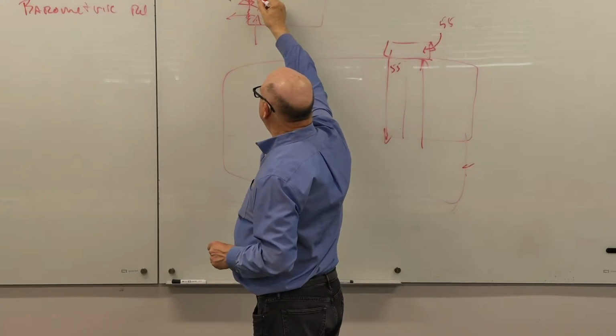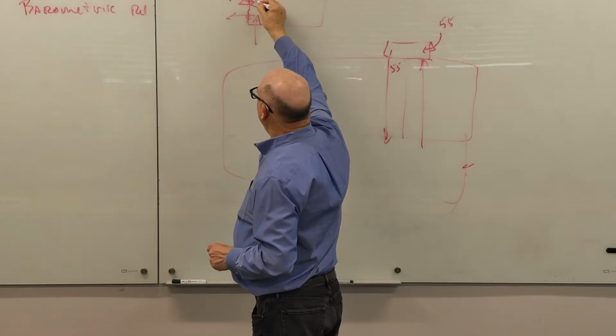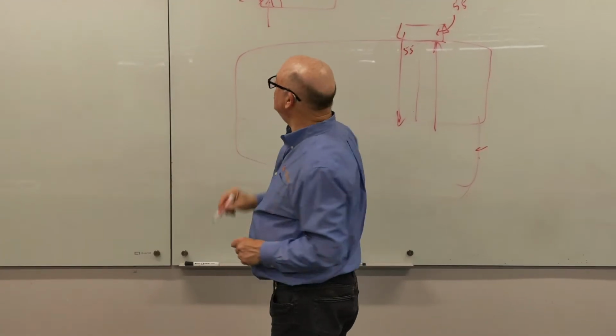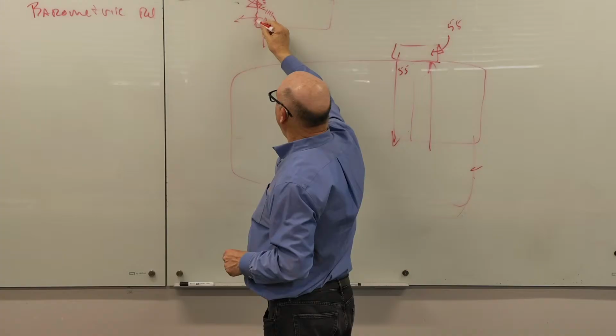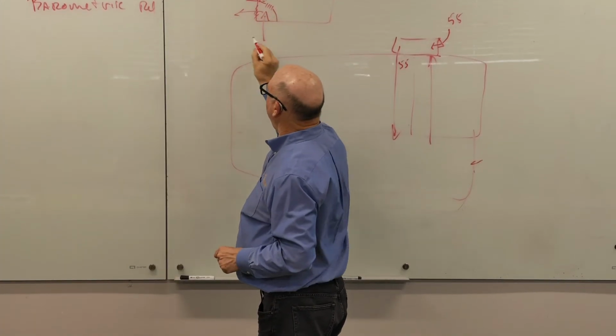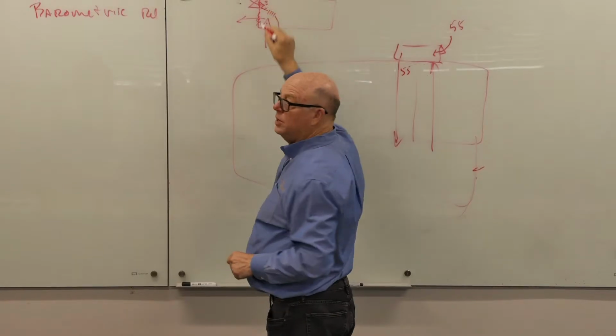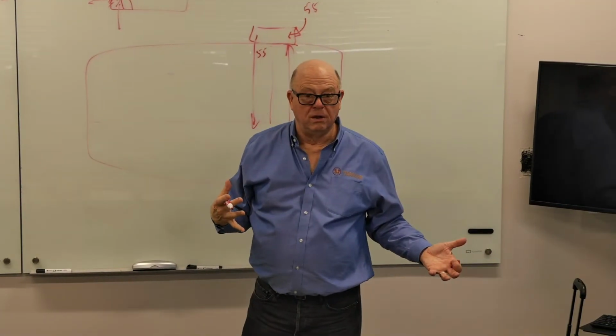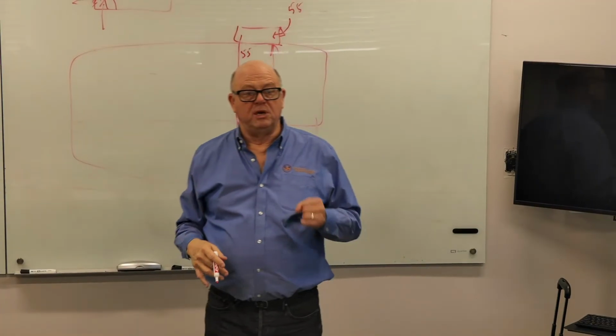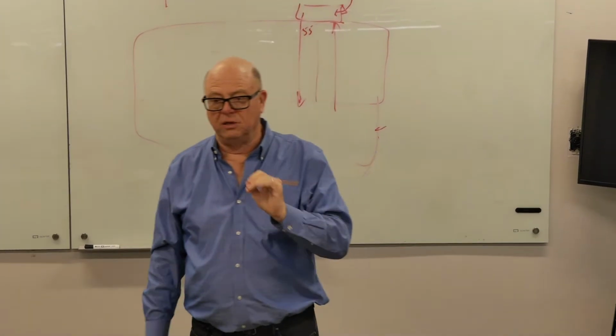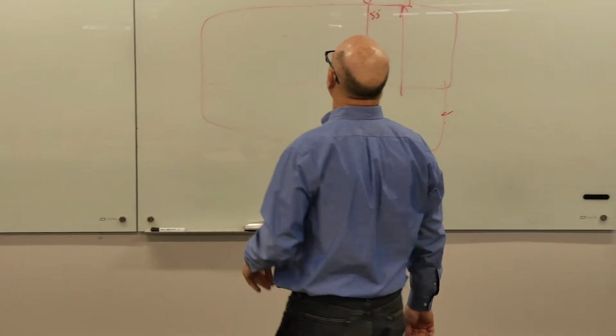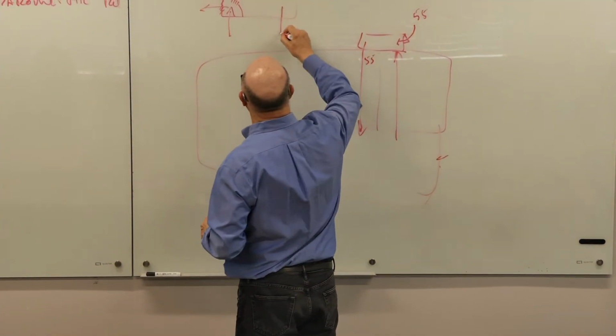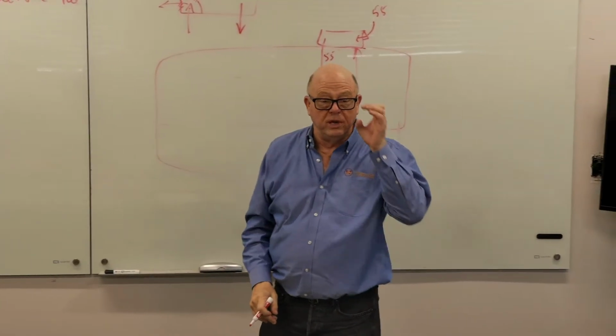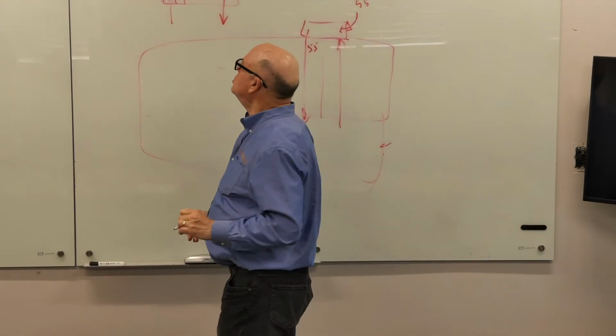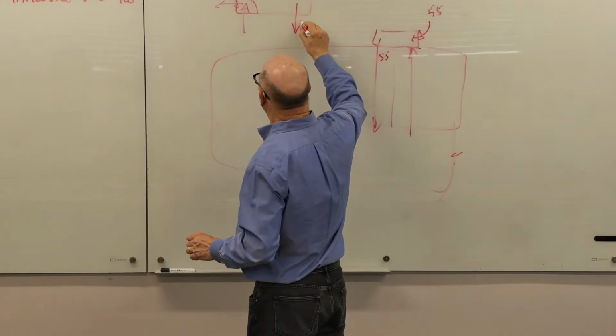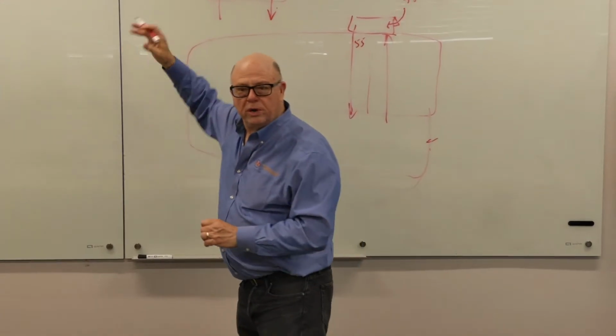And these dampers, and I'm going to draw them here even though this is seldom exactly where they're at, those dampers open at the same time that these dampers open. So as you're relieving that air out, you're now able to pull in more outside air. And because we have some of the best test and balance people in the industry, I can guarantee you that every single time we install a unit with an economizer, they set it up so that the supply CFM is correct when we're in economizer mode.